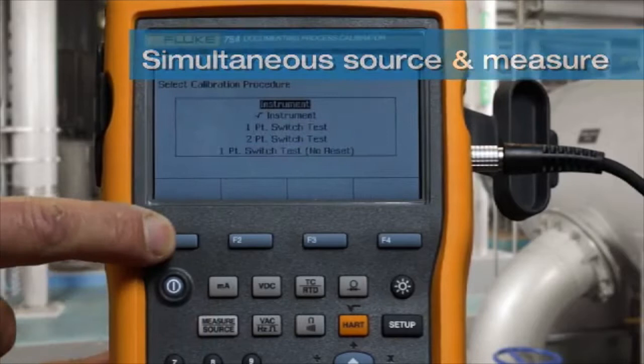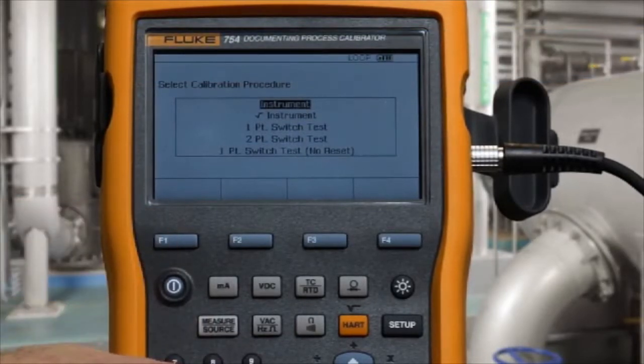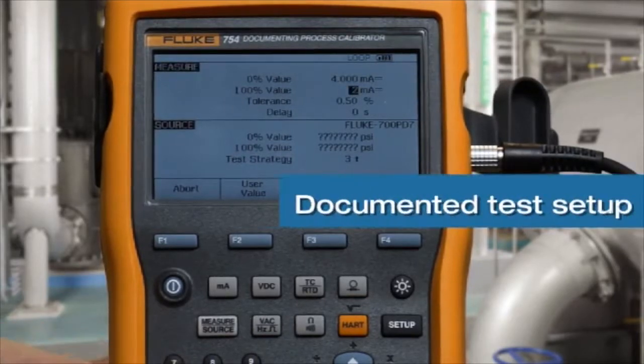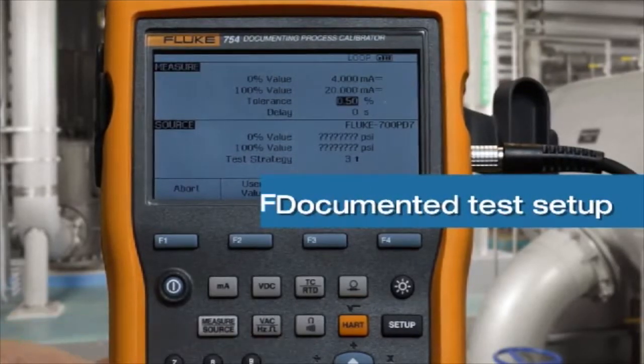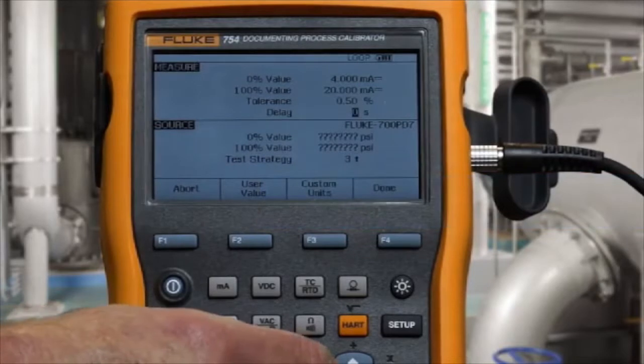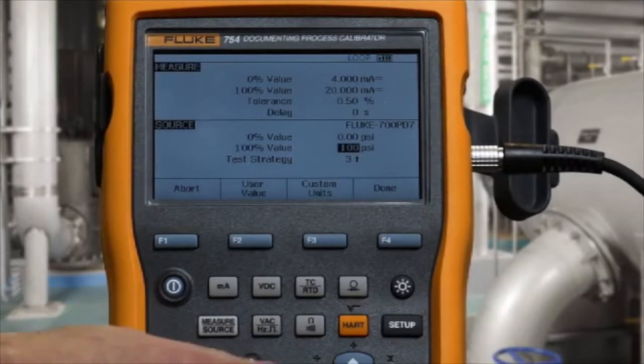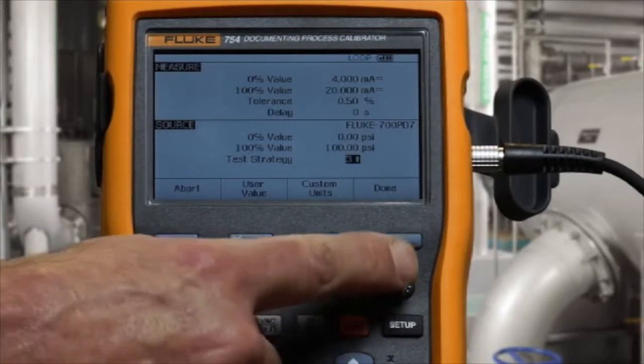Select as found for an instrument. We're going to measure 4 to 20 milliamps to a test tolerance of 0.5%, and we're going to source zero to 100 psi, and we're going to do a three-point test.